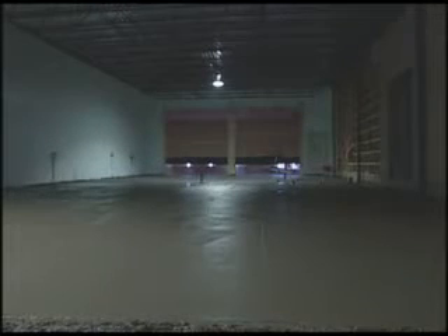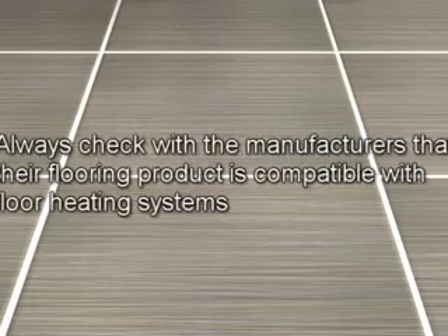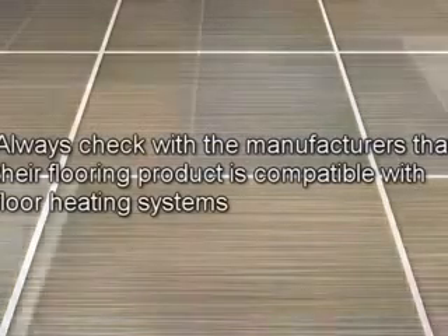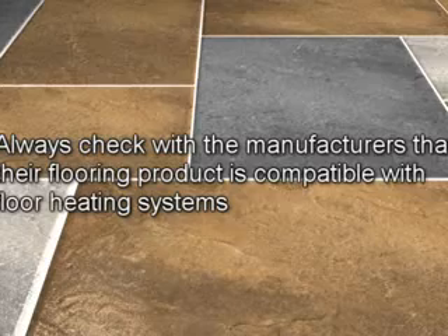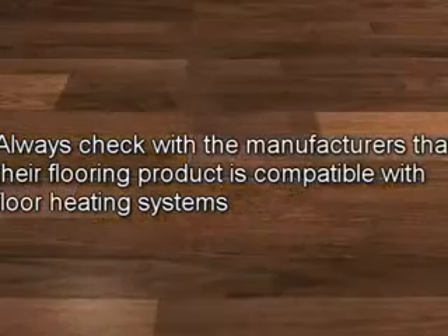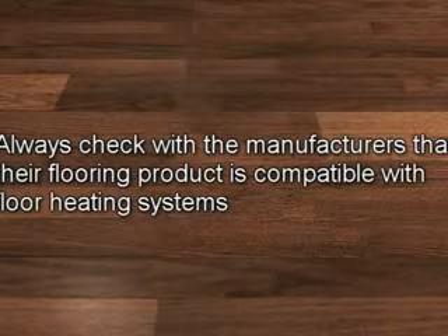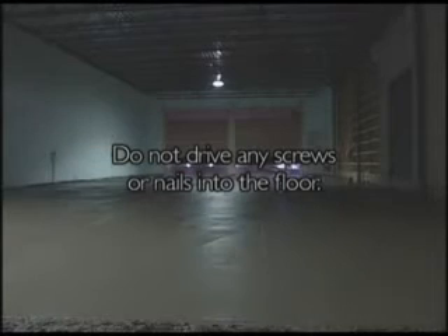When the curing period of your slab is over, repeat the insulation and integrity tests that were done earlier. You can then proceed to the installation of your floor covering. Ceramic tiles, natural stone, hard or flexible coverings can be used in combination with the green cable concrete. However, you should always verify with manufacturers that their flooring product is compatible with floor heating systems. Do not drive any screws or nails into the floor.